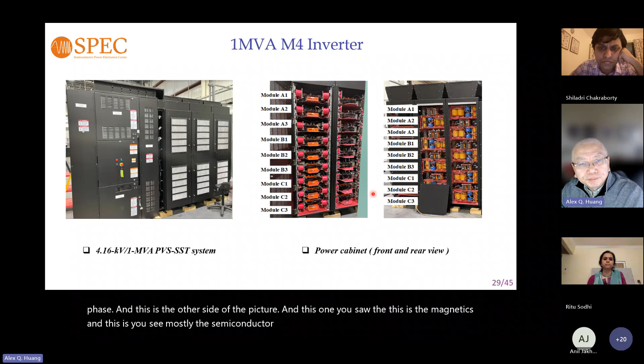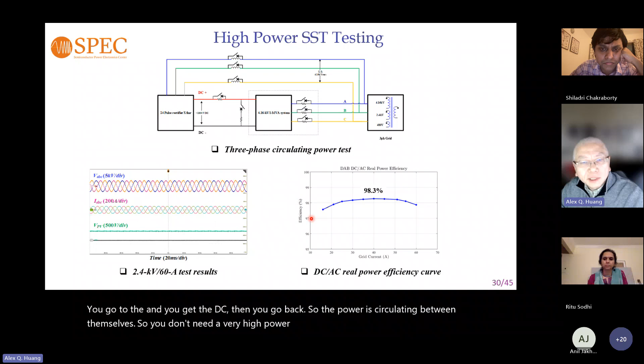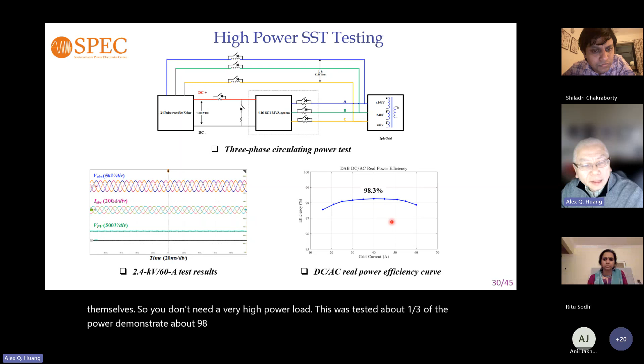Testing this is also difficult. Here's how we did the test — basically you circulate the power. Your AC grid comes in, you convert to DC, then go back, so the power circulates between themselves and you don't need a very high power load. This was tested at about a third of the power and demonstrated about 98% efficiency.